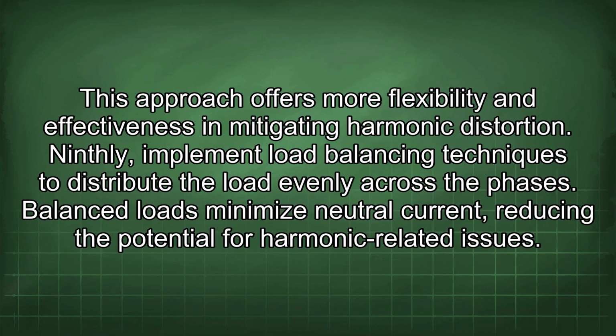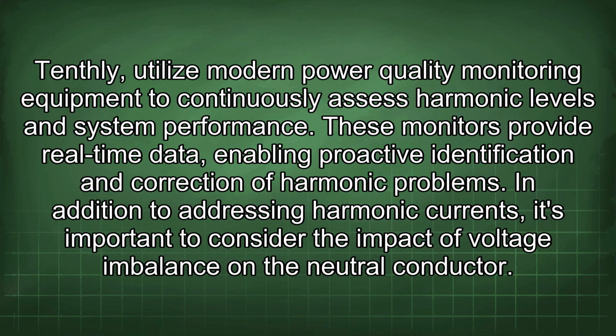Ninthly, implement load balancing techniques to distribute the load evenly across the phases. Balanced loads minimize neutral current, reducing the potential for harmonic-related issues. Tenthly, utilize modern power quality monitoring equipment to continuously assess harmonic levels and system performance. These monitors provide real-time data, enabling proactive identification and correction of harmonic problems.